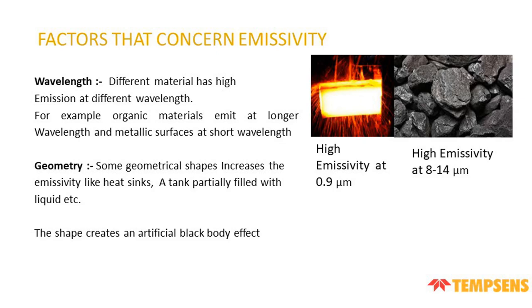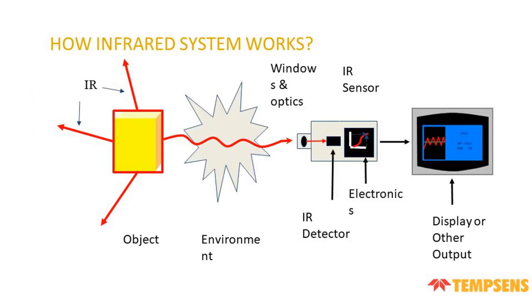More concerns about the emissivity: wavelength. Different materials have high emissivity at different wavelengths. For example, organic material emits at longer wavelength and metallic surface at shorter wavelength. Geometry: some geometric shapes increase the emissivity, like a heat sink or a tank partially filled with liquid. The shape creates an artificial blackbody effect. How does an infrared system work? IR comes from the object through the medium of the environment and arrives on the optics. We use a special algorithm to display the temperature.